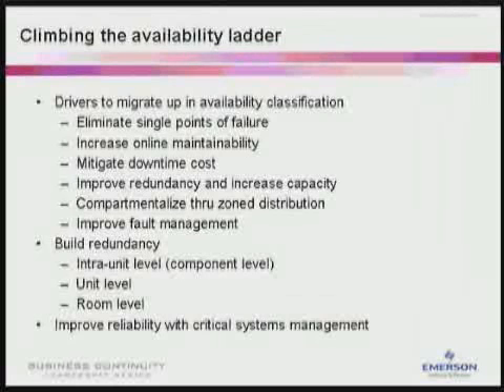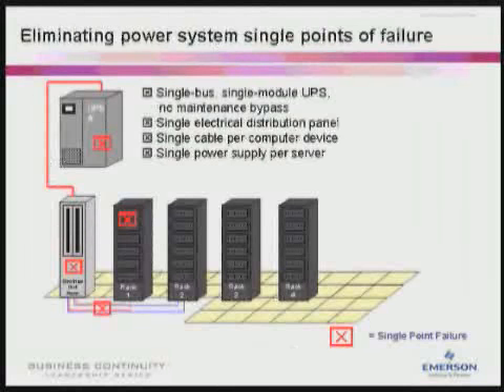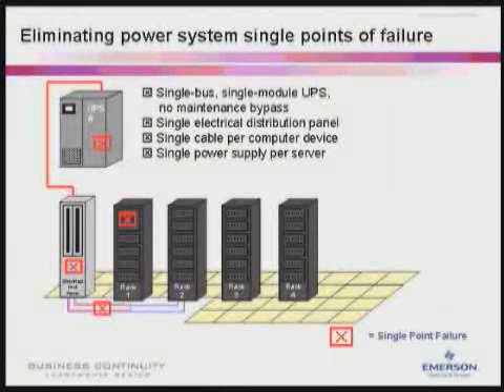Let's look at eliminating single points of failure in a basic data center. This data center has a single bus, single module UPS, no maintenance bypass, single distribution out to those loads, single cable per computer device, and single power supply per server. A number of single points of failure.